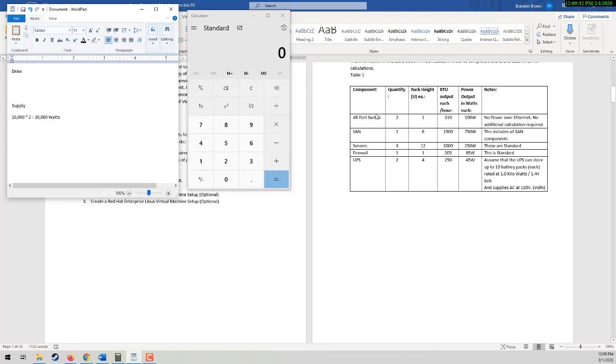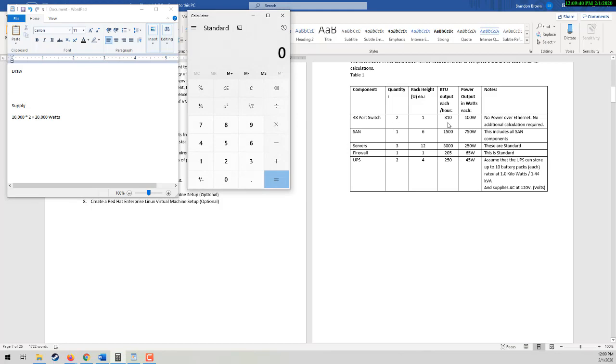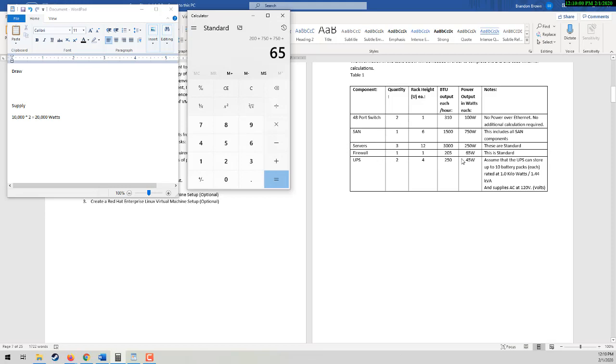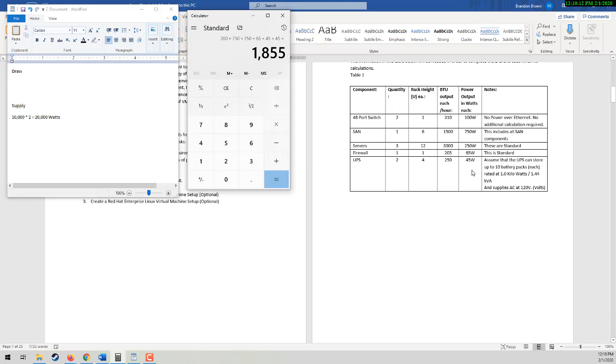Our draw is going to be the calculation of all of these power outputs for the different components. So here's where the calculator comes in handy. We have 2 times 100, that's 200, plus 750, plus another 750 because 3 times 250 is 750. One firewall at 65 watts, and then the two UPSs at 45 watts. Now here is a gotcha. When the power is cut off, your UPS will no longer be drawing power. So it won't be drawing 45 watts for itself. So take that 90 watts back. And that is your draw.